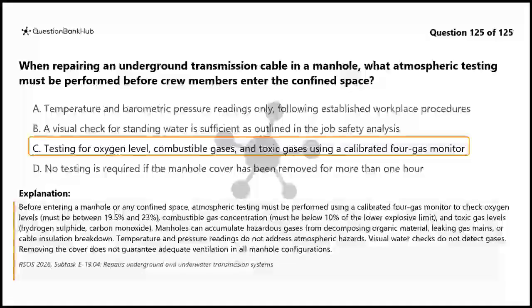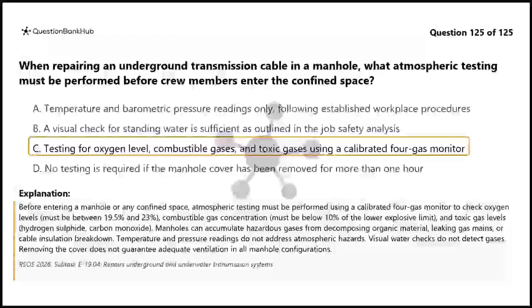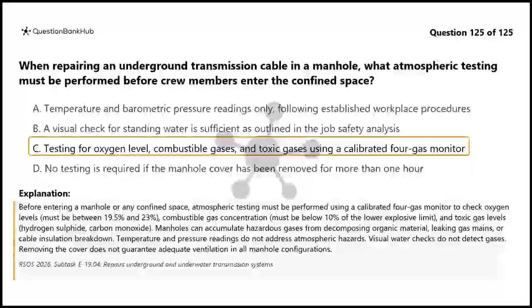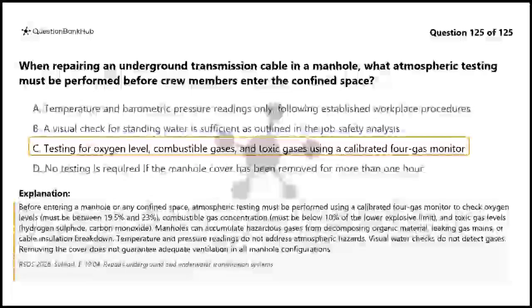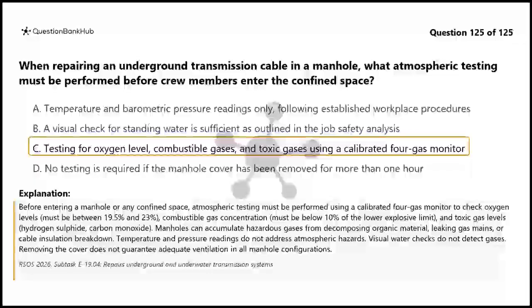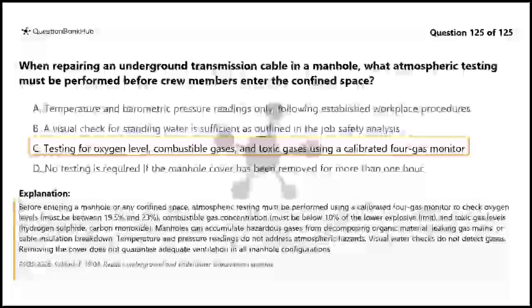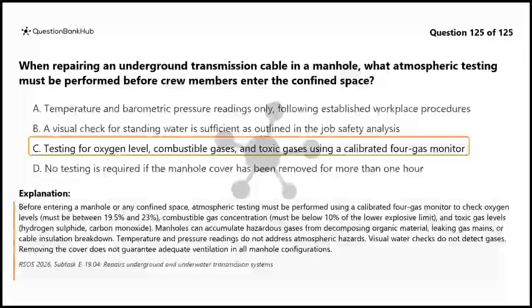Before entering a manhole or any confined space, atmospheric testing must be performed using a calibrated 4-gas monitor to check oxygen levels, which must be between 19.5% and 23%, combustible gas concentration, which must be below 10% of the lower explosive limit, and toxic gas levels, hydrogen sulfide and carbon monoxide. Manholes can accumulate hazardous gases from decomposing organic material, leaking gas mains, or cable insulation breakdown. Temperature and pressure readings do not address atmospheric hazards. Visual water checks do not detect gases. Removing the cover does not guarantee adequate ventilation in all manhole configurations.